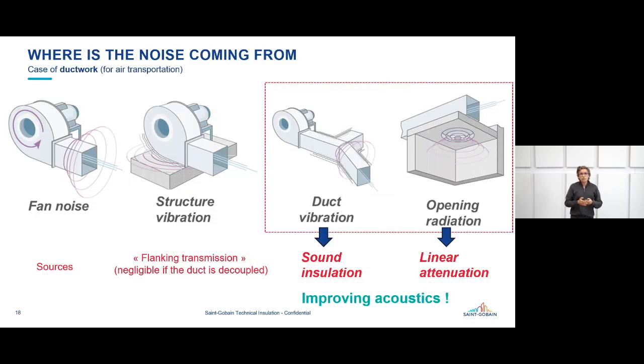Now let's come a little more into the detail of a typical ductwork. Imagine we are building a ductwork system and asking ourselves, where is the noise coming from? On the left, starting from the beginning, we have the fan noise, our typical source in this field. The first acoustic topic we face is what I call structure vibration, simply due to the fact that part of the duct vibration can be transmitted to the surrounding system, which can be floors or walls. This is what I call flanking transmission, which can be negligible in practice if the duct is correctly decoupled from its environment.